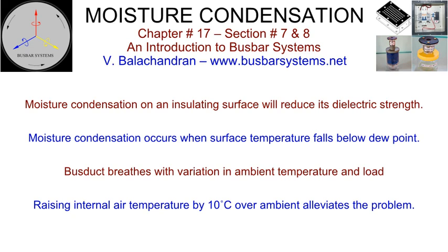When condensation occurs, moisture along with the dust particles will settle on the surface of the insulator and provide a path of low impedance for leakage current to flow and result in tracking. The dielectric properties of some insulators can deteriorate with the absorption of moisture.